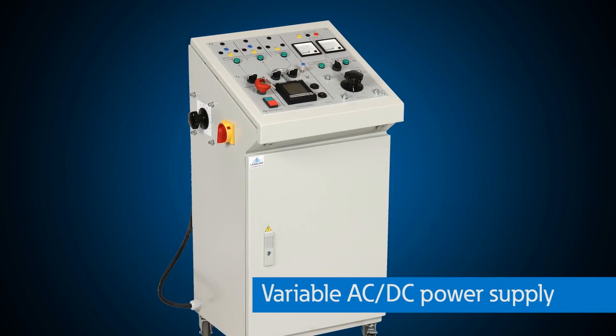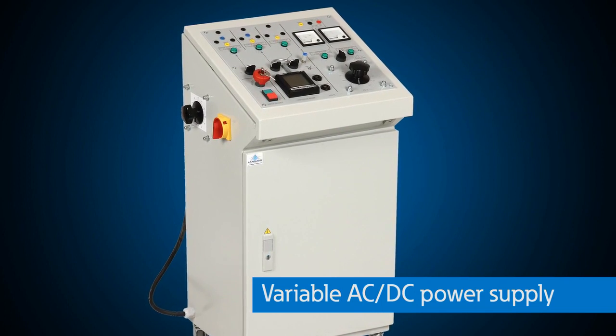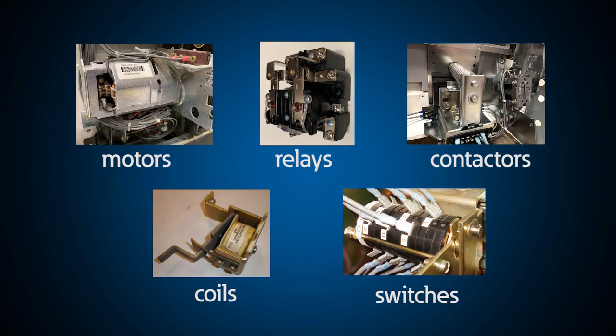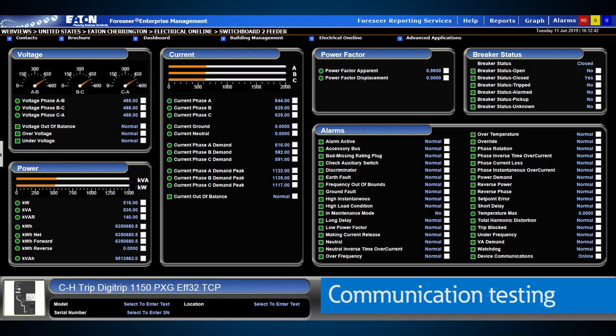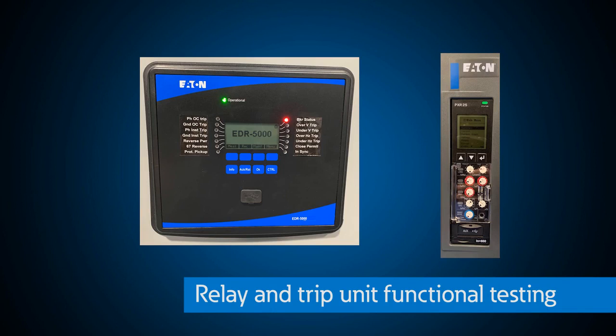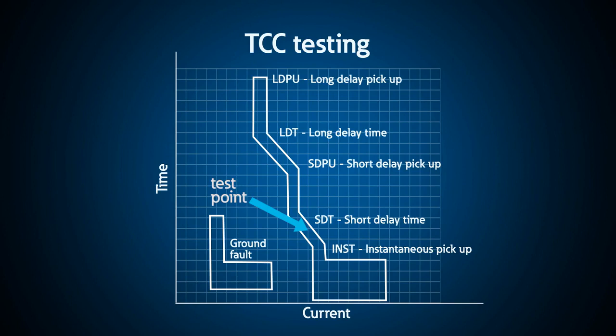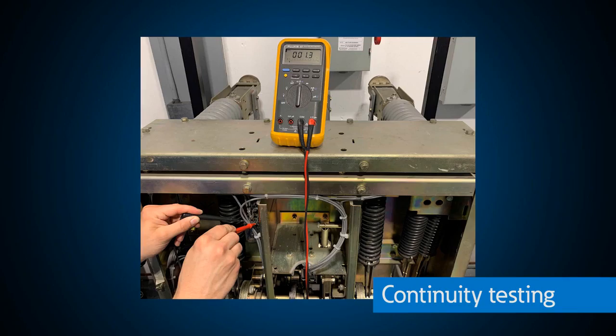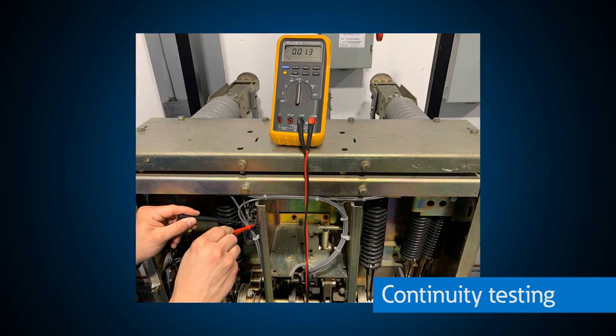This test is often referred to as Doble testing, as Doble is the manufacturer of the typical equipment used for this testing. For other equipment, including circuit breakers, contactors, and other control equipment, using an AC or DC variable power supply, tests are performed to verify the operation of all the electrical components on a piece of equipment, including motors, relays, contactors, coils, and switches. Some of the tests include communication testing, including testing and verifying all communicating devices to ensure that they are sending and receiving information as designed. Relay and trip unit functional testing, which includes testing the functionality and verification of settings of these protective devices to ensure expected operation. Continuity testing is a more simplified test compared to ductor testing, where wires, fuses, and windings are evaluated for point-to-point continuity to ensure expected connectivity.